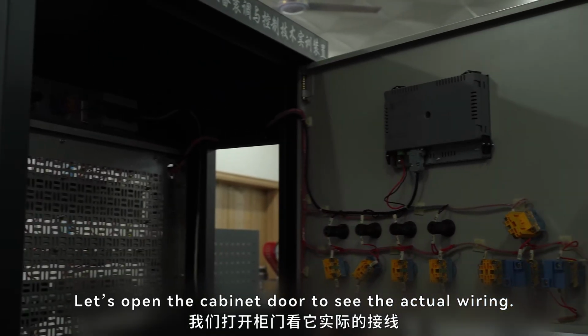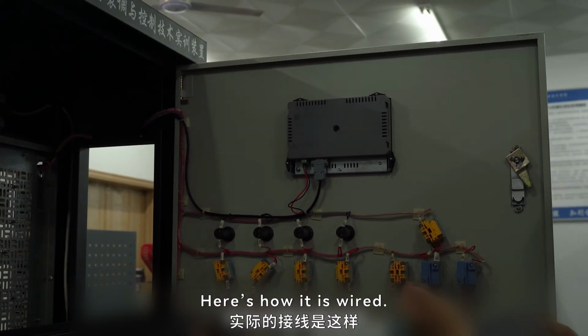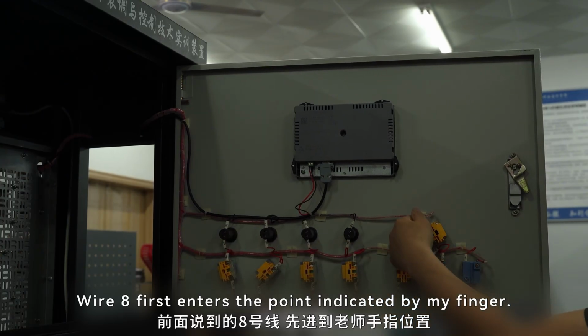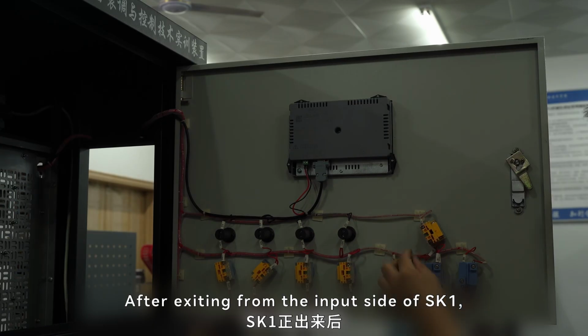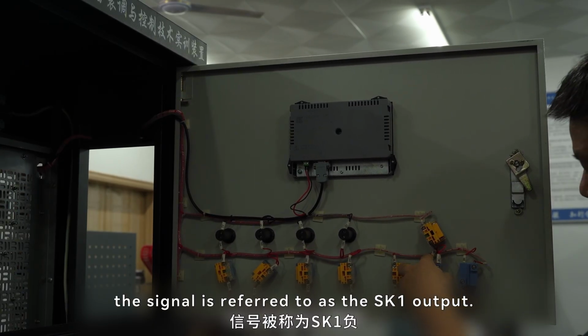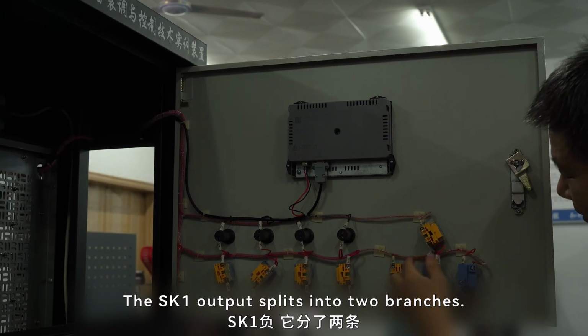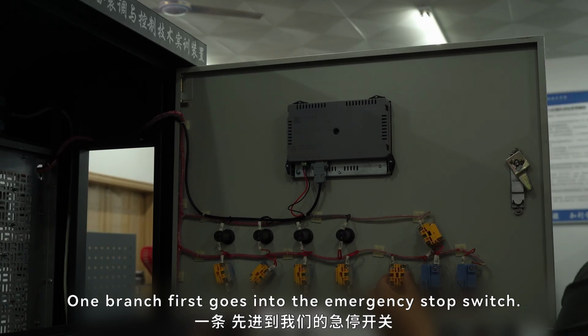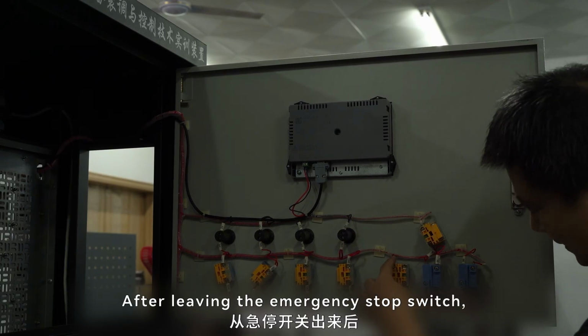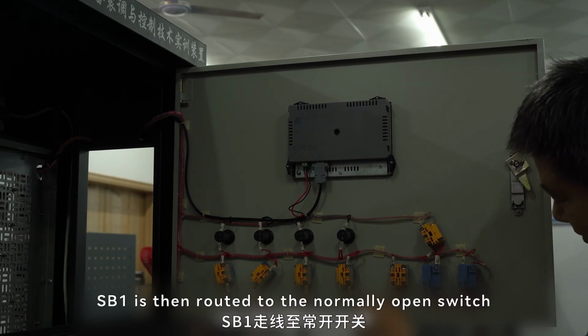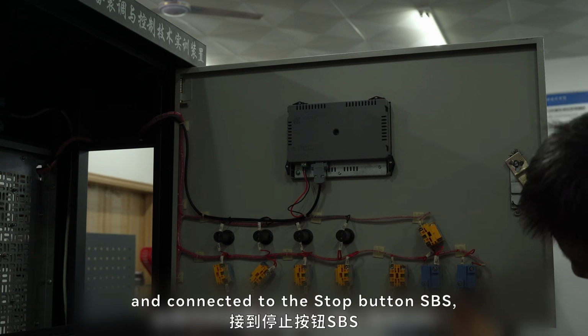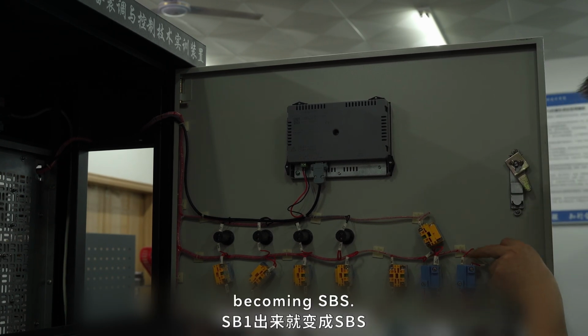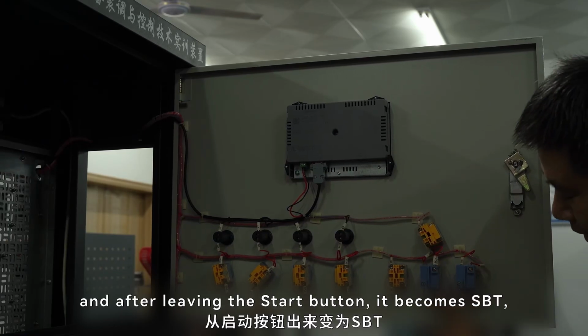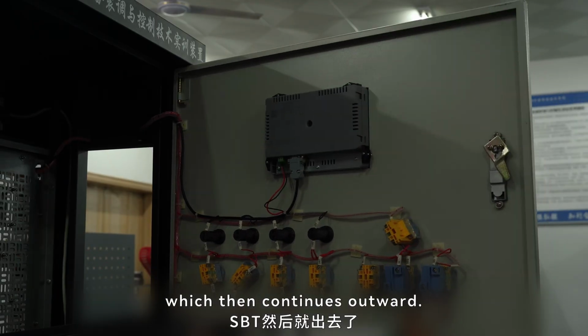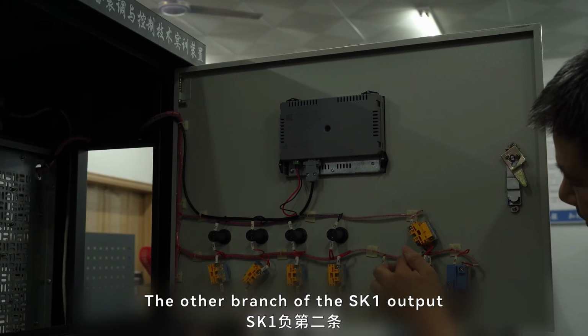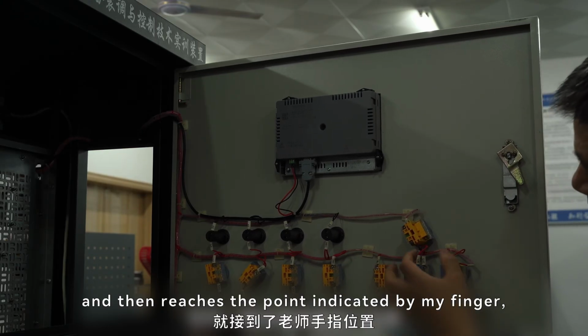Let's open the cabinet door to see the actual wiring. Here's how it is wired. Wire 8 first enters the point indicated by my finger. After exiting from the input side of SK1, the signal is referred to as the SK1 output. The SK1 output splits into 2 branches. One branch first goes into the emergency stop switch. After leaving the emergency stop switch, it becomes SB1. SB1 is then routed to the normally open switch and connected to the stop button SBS, becoming SBS. SBS is also connected to the start button, and after leaving the start button, it becomes SBT, which then continues outward.